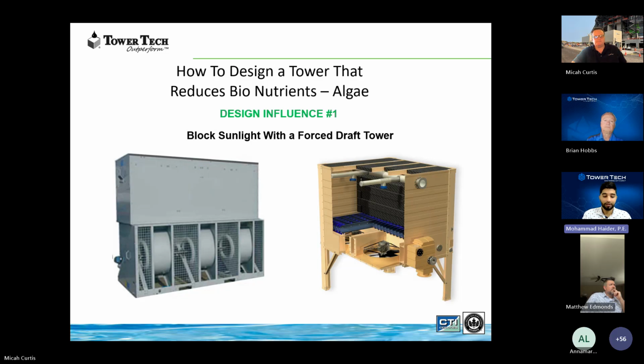Yeah, so the number one way to reduce algae growth is recognizing that algae growth is a direct result of organic particles and their exposure to sunlight in warm water, such as a 70 to 100 degree Fahrenheit environment. So the number one thing you can do to reduce algae growth is to remove that sunlight from the equation. If you have a tower that doesn't have an exposure to sunlight, then even if you have organic particles and the optimal temperature, you're not going to have algae growth. So yeah, blocking sunlight in a tower.